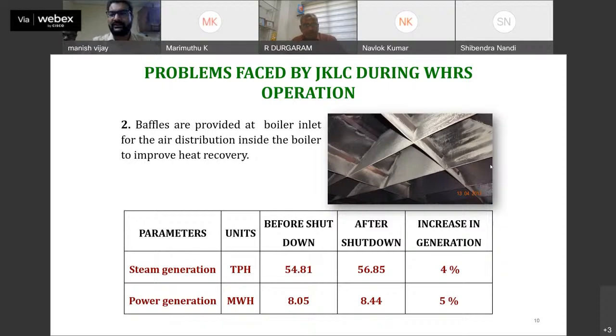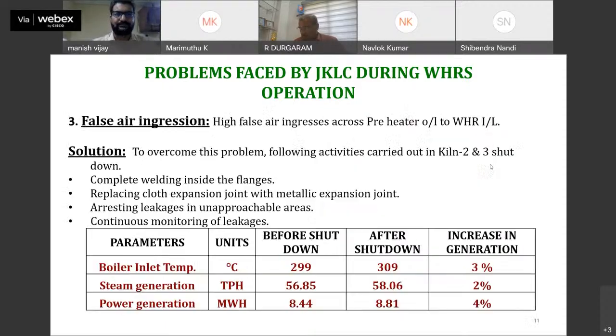On the PH side, it was higher than the design temperature. It simply means that the gases were bypassed from the boiler. To get rid of this, we discussed with the suppliers, and our internal team decided to provide a path for the gases to get the maximum recovery from the gases to the water tubes through the steam tubes. By installation of the baffles, we improved our power generation in the boilers by around 5%.